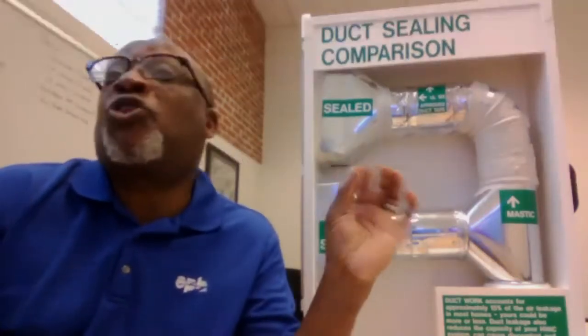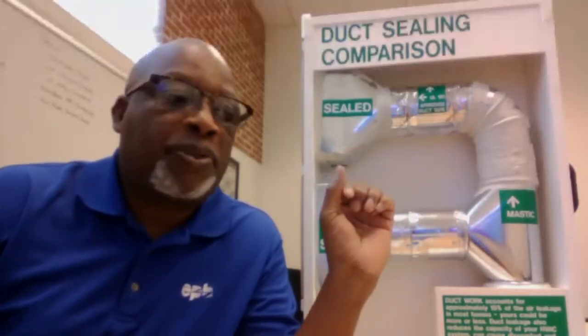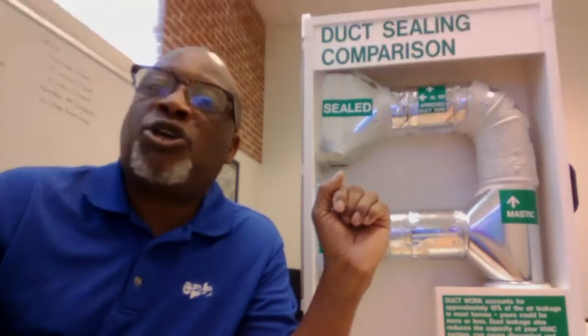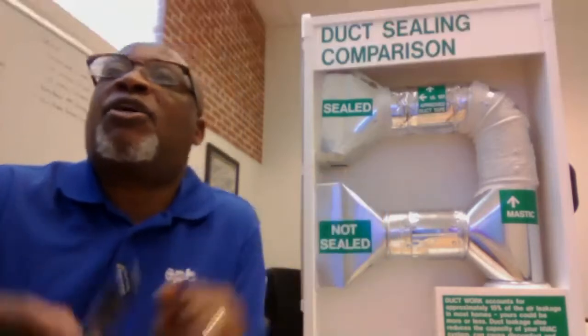You put one thermometer at the return where the air filter goes, and you take the second one and put it on the registers, on the vent. Now, the air going in, being processed and blowing out, you should have a 15 to 20 degree difference in temperature. So if the air is going in at 60 degrees and you're on air, it's supposed to be 15 degrees cooler, okay? And if the air coming out at that register is at 55, then you know it's only 5 degrees, and that's not good, okay? Those things would end up being low on Freon, some of the telltale signs, or your unit just not operating properly, okay? Now, so back to the ductwork.